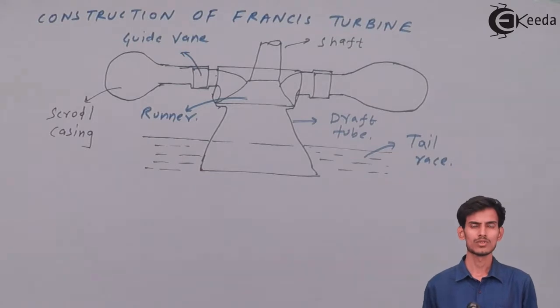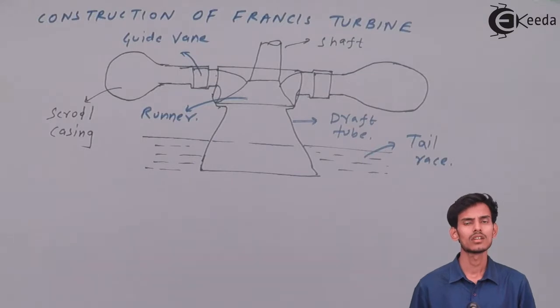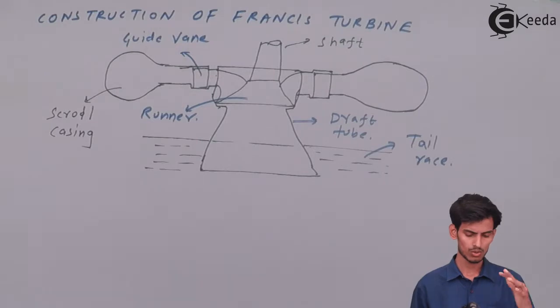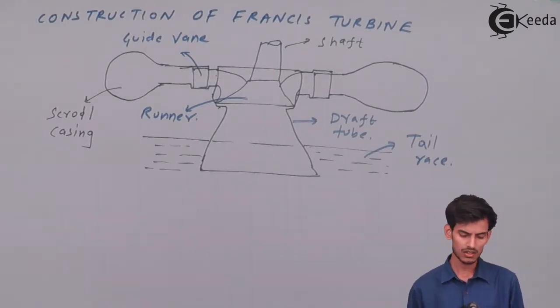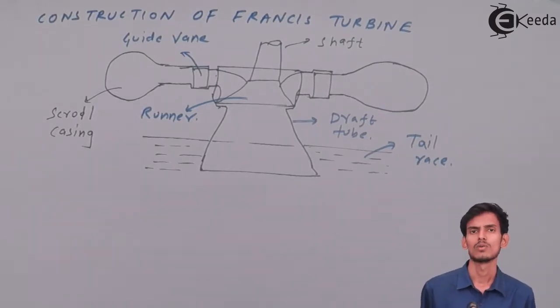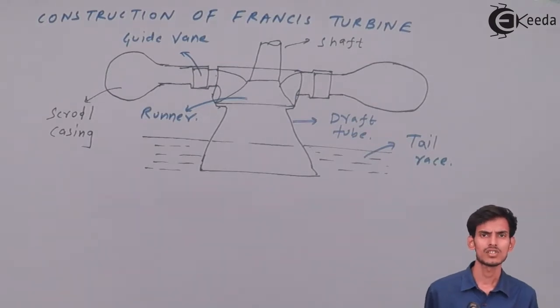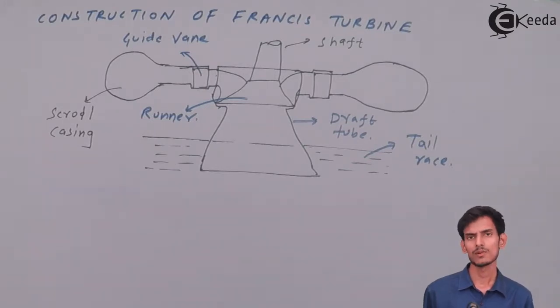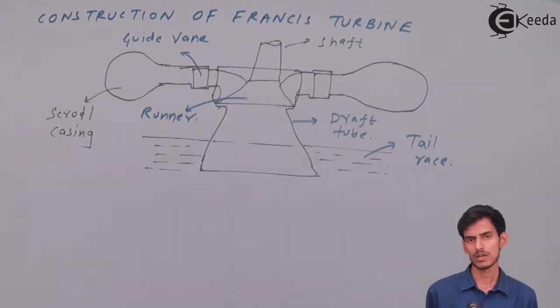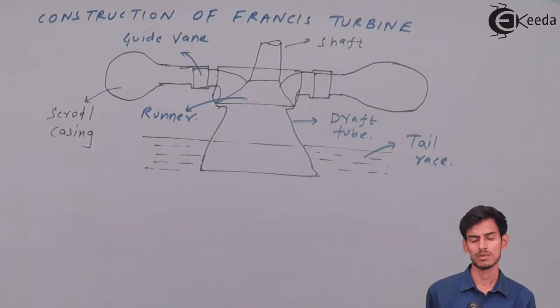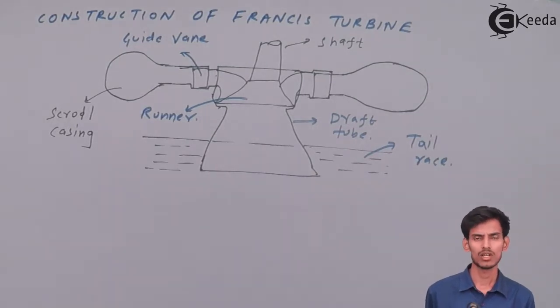The guide vanes are made of aerofoil shape so there are no losses. Once water enters the runner, it generates power, and then the remaining water passes through the draft tube into the tail race. The draft tube is very useful in Francis turbine because when water comes out of the runner, it has some kinetic energy and the pressure is generally below atmospheric pressure, creating chances of cavitation — bubbles and flow separations. The draft tube is a diverging tube, so as water flows down, the pressure increases, which prevents cavitation and separation.